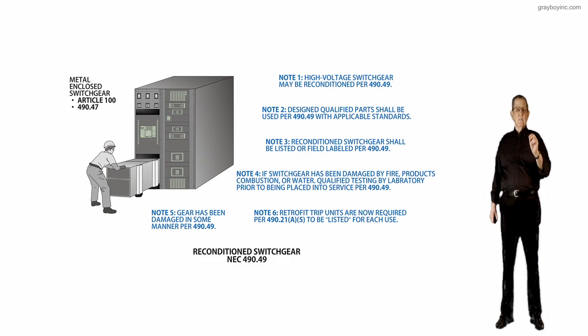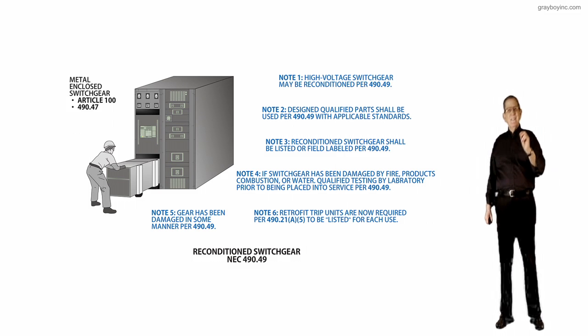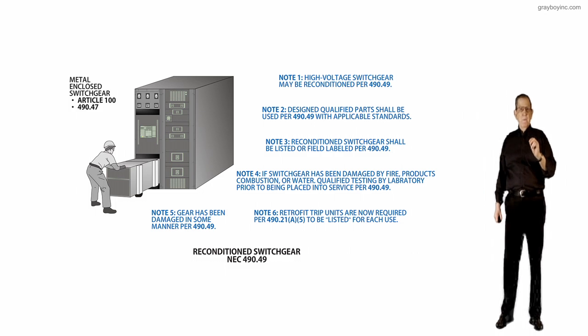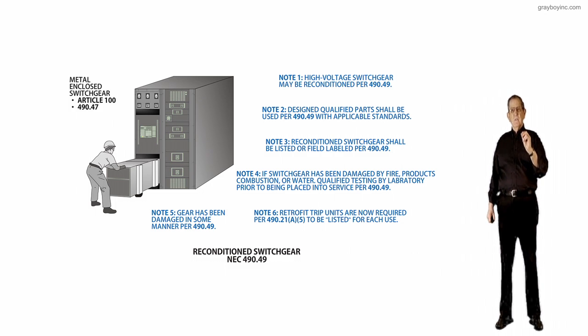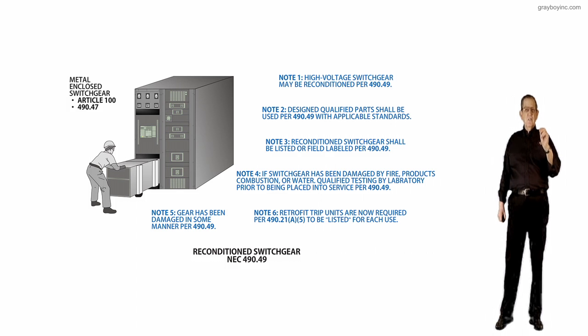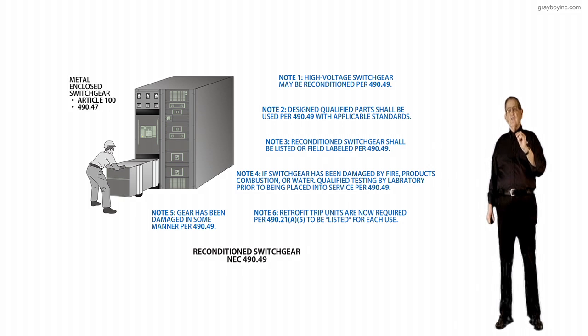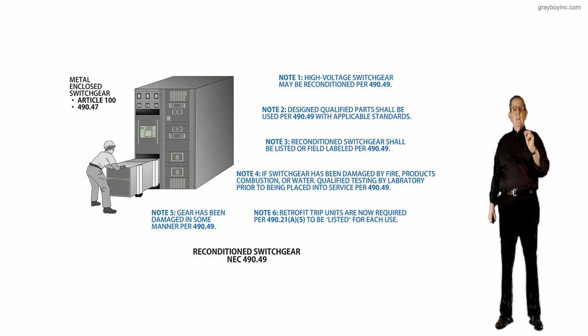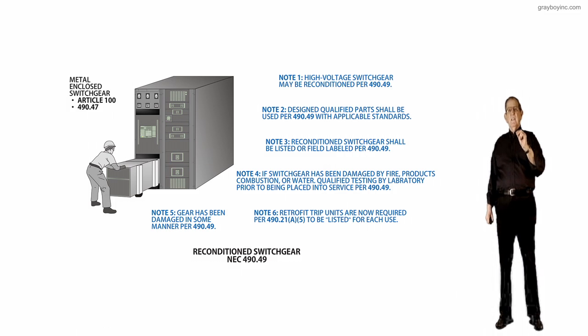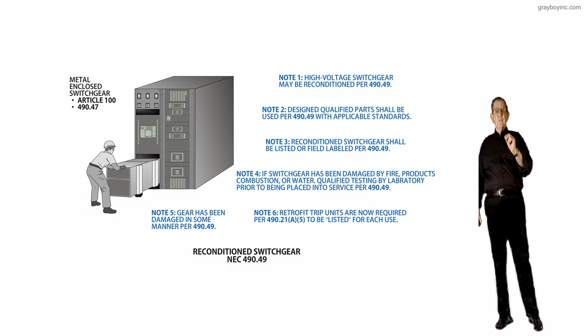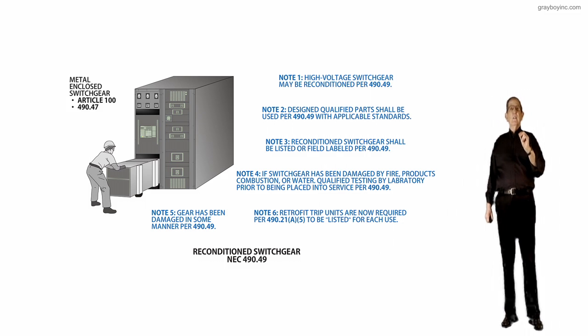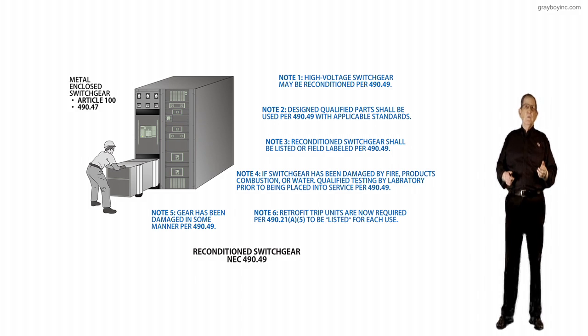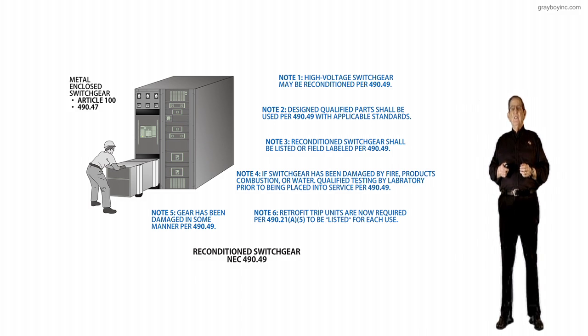Now, notice this, it specifies this in 490.49 of the NEC. The text also includes provisions on parts selection and recondition procedures from the NEMA reconditioning paper written for such conditions. These provisions are actual requirements that appear under its definition subhead. They must be located here and not in the actual definition, so we understand what this new section is really all about. Now, the first thing I'd like to review is the metal enclosed switchgear, right to the left.